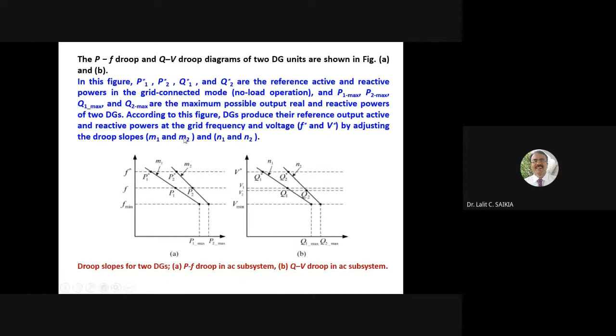In addition to the aforesaid droop method, direct droop control is used for non-dispatchable DGs such as wind power and PV systems, and inverse droop method is also used. In this strategy, the inputs of the droop controller are the PCC voltage amplitude and frequency, and the outputs are the reference active and reactive power.